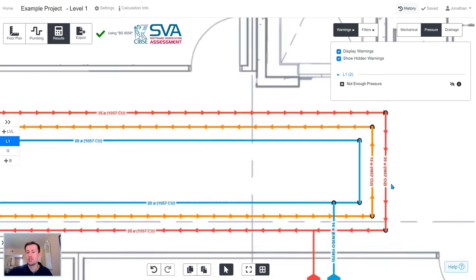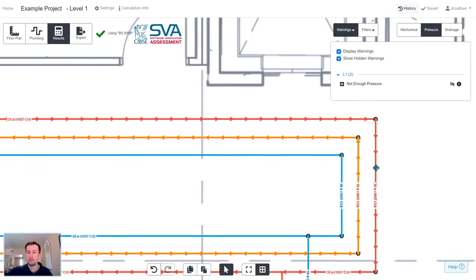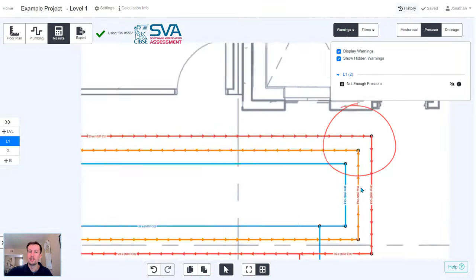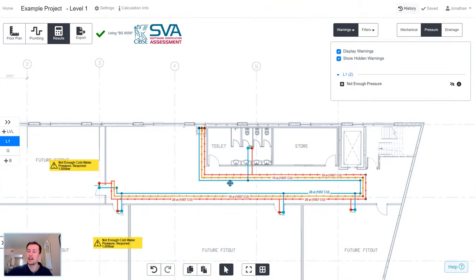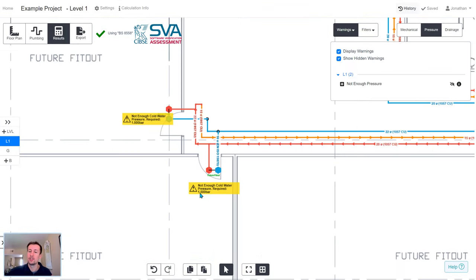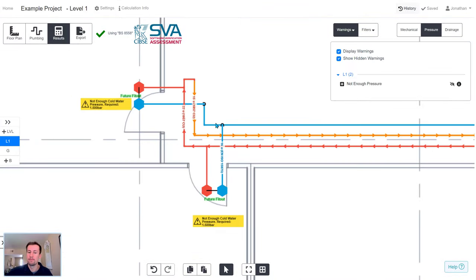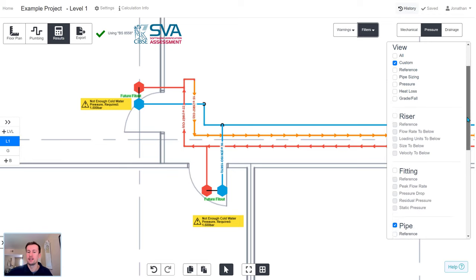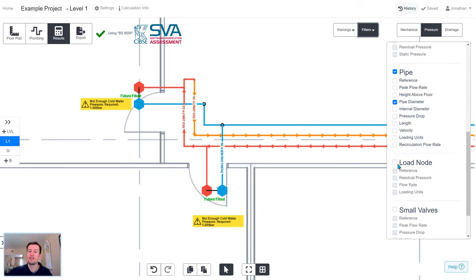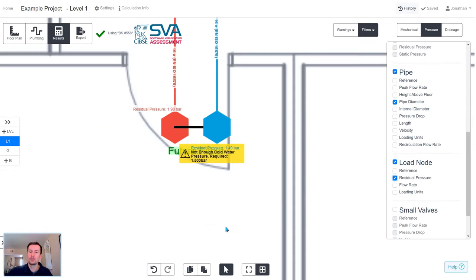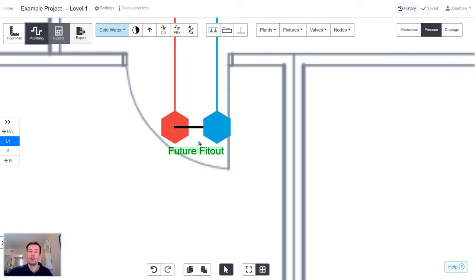If any of the changes cause problems, the design will flag these so you don't miss them. Here we can see that by adding extra bends and increasing the pipe lengths in Revit, it's caused us to get non-compliant pressures in some areas of the design.